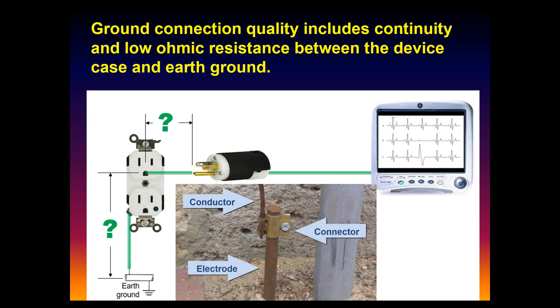If you're encountering devices behaving flaky and can't figure out what's going on, get a power plug, connect the neutral and the ground to your multimeter, and measure that voltage. Ideally it should be very close to 0. If it's less than about 2 volts, it's probably okay. But if that voltage gets too high, it implies connection problems, which can create very unstable, funky behavior in some devices.